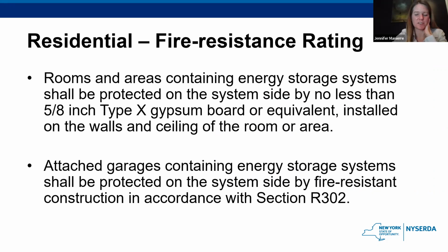Much like the commercial systems, residential also needs some sort of fire protection. So the code outlines that they need to be protected on the system side by no less than 5/8 inch type X gypsum board or equivalent on both the walls and ceiling of wherever it's installed. Attached garages containing the systems also need to be protected on the system side by some sort of fire resistant construction in accordance with section R302 of the code, which I believe is saying that it's like a 1 hour firewall, essentially.